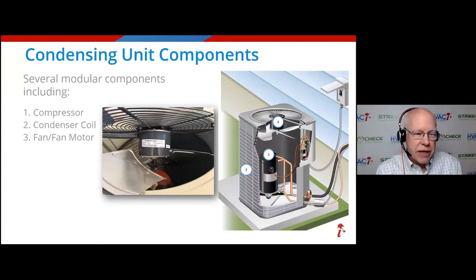This is where you've got to pay attention. That fan is designed to pull ambient air through and across those coils, and then it ejects it out of the top. So that heat you're feeling when you put your hand above number three is the heat that, just moments before, was in the refrigerant. Remember from a few minutes ago, heat moves to cold and not vice versa. The refrigerant is warmer than the air that's being pulled through it. So the heat leaves the refrigerant, physically goes into the air, and is ejected out of the top.